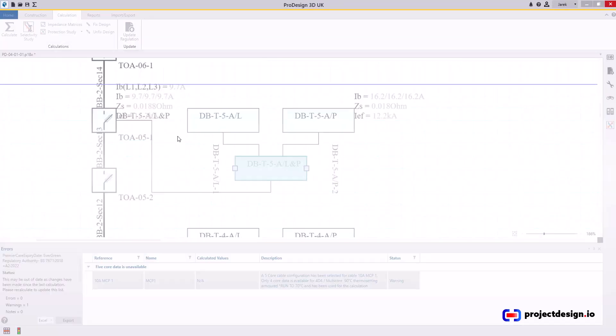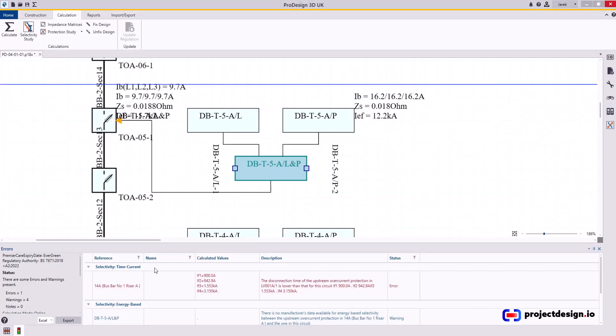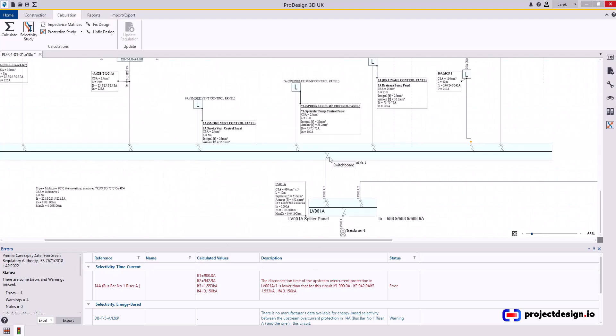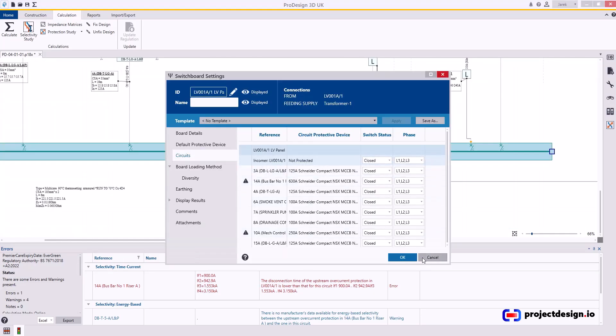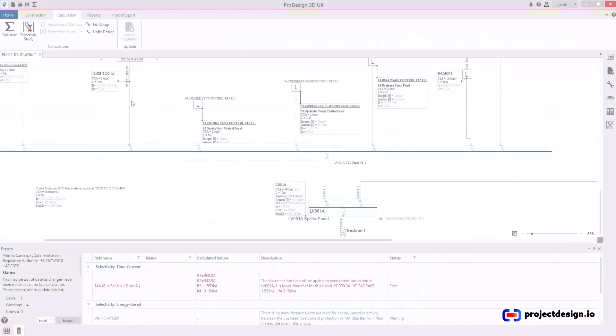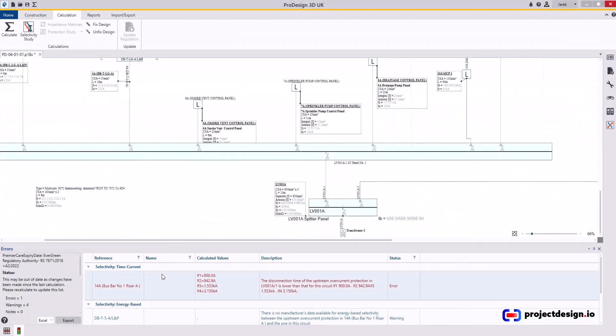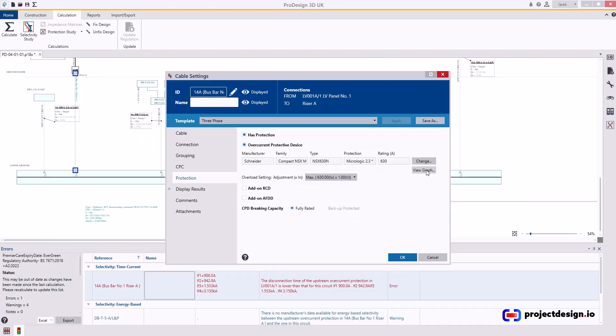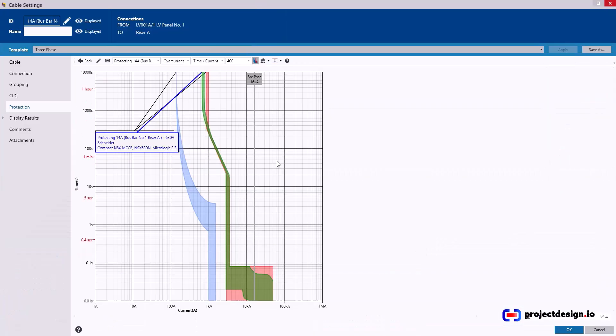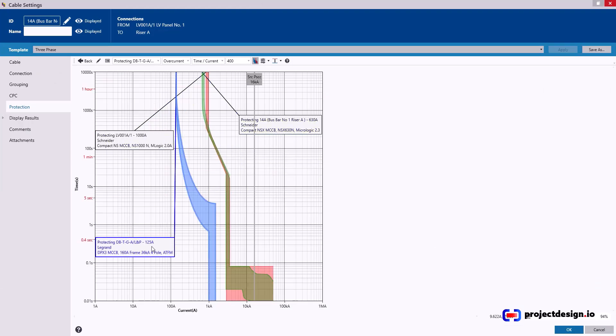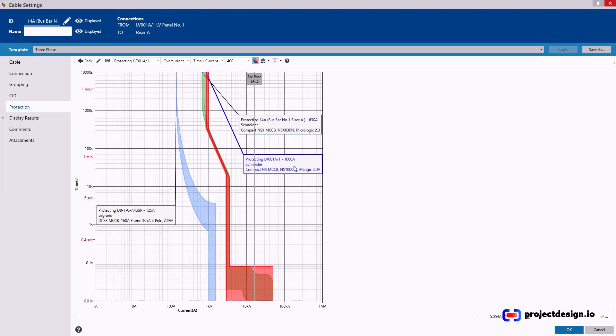Now let's select selectivity study. I've got one more problem. The disconnection time of the upstream overcurrent protection device in LV001A is lower than the circuit. So upstream protection. This device here is probably incomer. Let's check. Incomer not protected. So this warning message says that this device here has problem with time current selectivity with that device there. The way to check, double-click on the cable, go to protection, go to view graph.